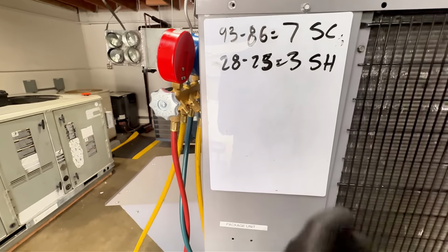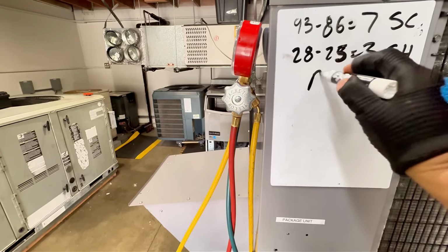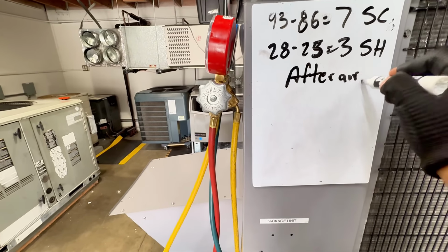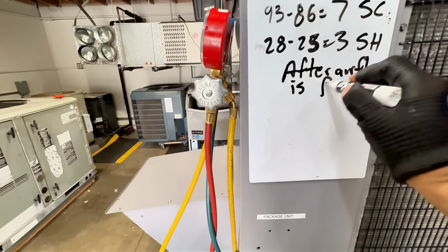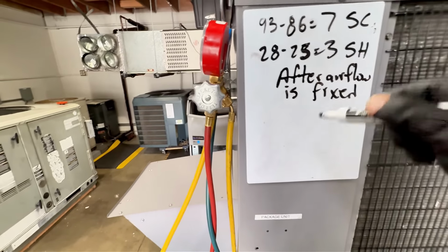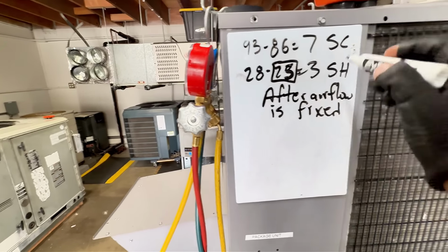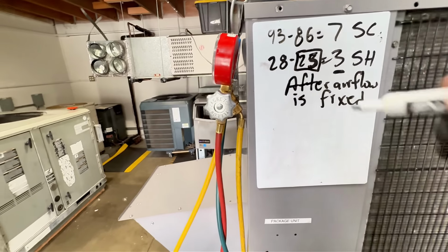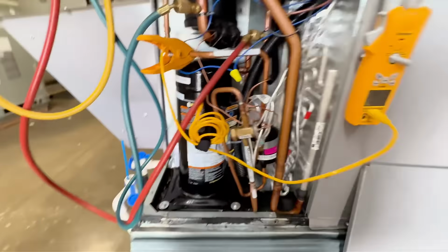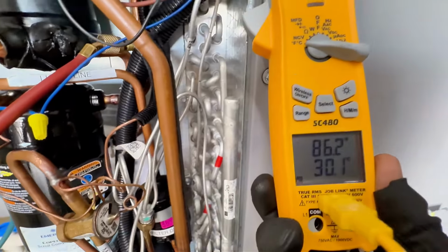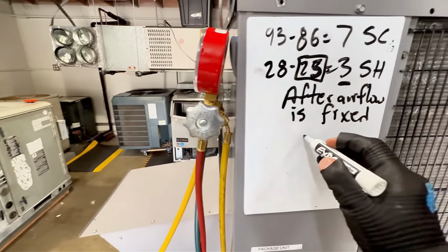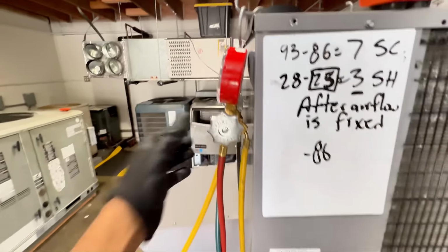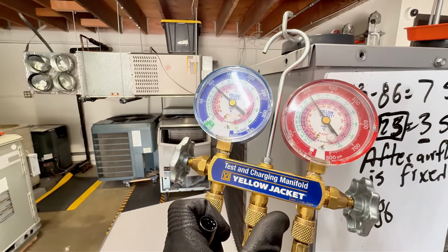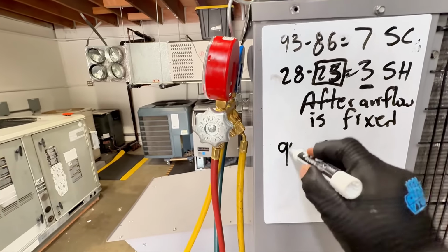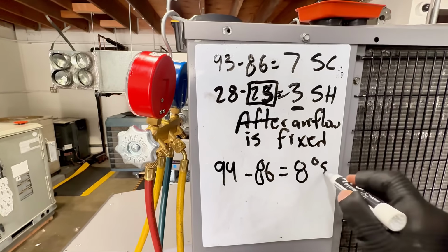Okay, so now let's recalculate everything. This is after airflow is fixed. So this was before, this is after. I want you to pay attention to the evaporator temperature and my superheat. Other stuff is going to change, but let's check our liquid line temperature, and the subcool is not going to change too much. It's 86. So my liquid line temperature is 86. Let's check our condensing temperature. 94. So maybe a little bit. I have an 8 degree subcool.